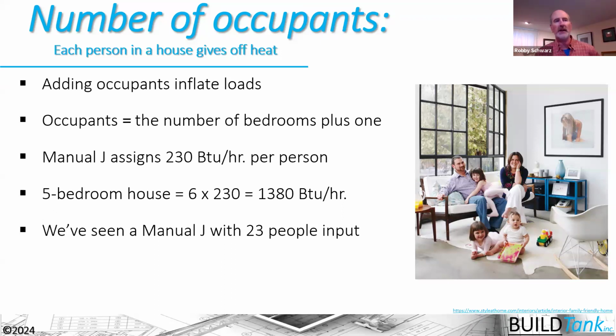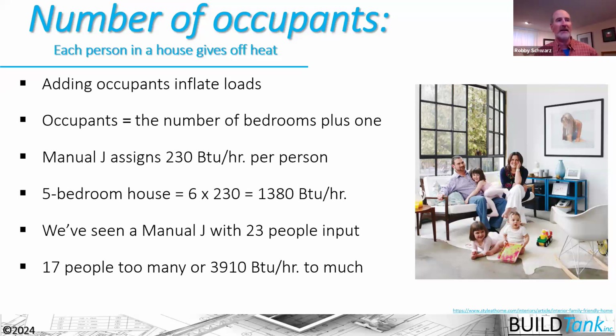So we've seen a Manual J that, for example, entered 23 people into the house. So we see that jump from 1,300 to almost 3,900 BTUs in that house. I guess that was for 17 people here. But you can see that it is a subtle way of potentially manipulating the heating load or cooling load for that house. It's something that we want to guard against, because the result in this case was adding an additional 1/4 ton of air conditioning to that particular house.